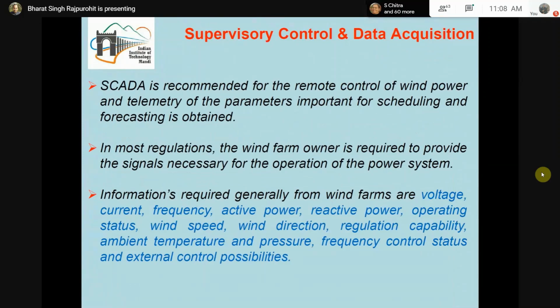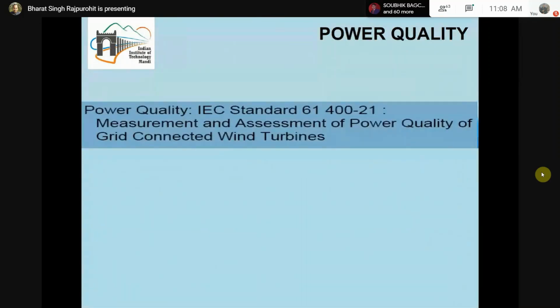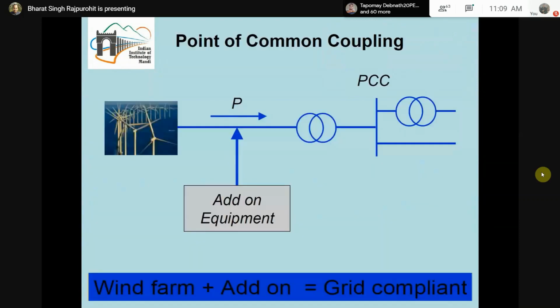Now let me come to power quality. Power quality standards need to be met. IEEE 519 is there. IEC standard 61400 is also there for wind turbines. It depends on which country and which standard they are following. Generally, India follows the IEC standard, so that is expected to be met whenever grid-connected wind turbines are there. Overall, at the point of common coupling, where wind or solar infrastructure meets the grid infrastructure, all these requirements must be met.